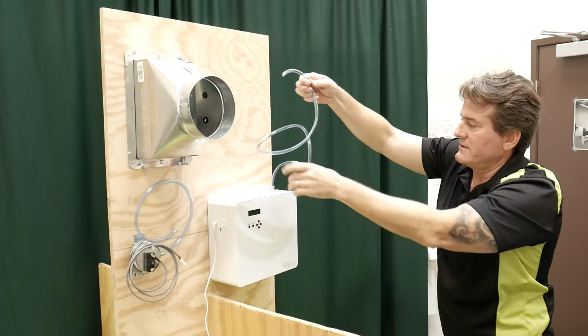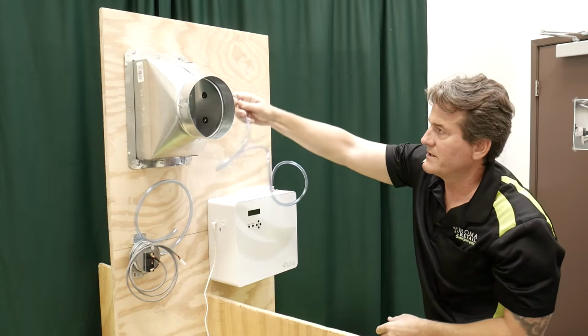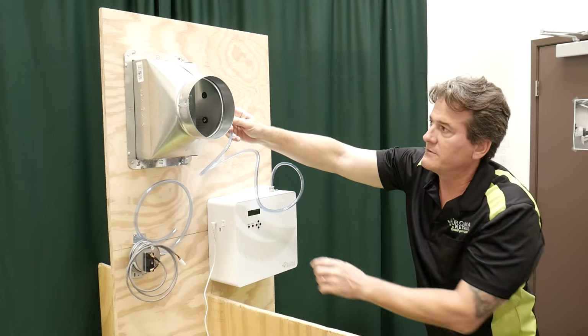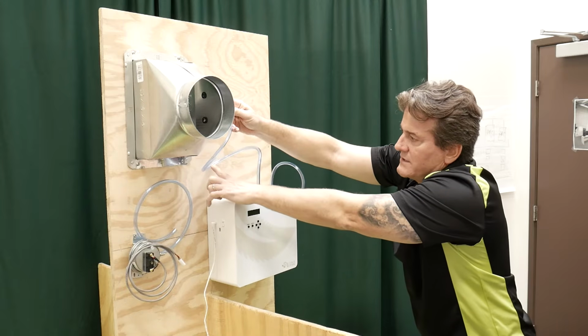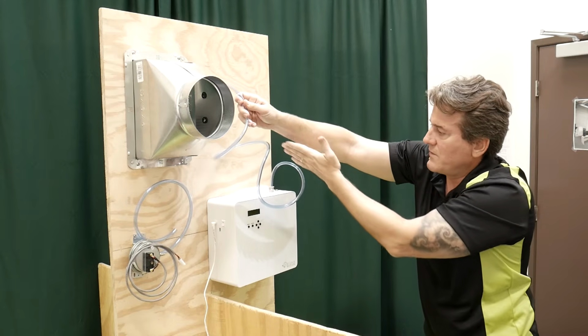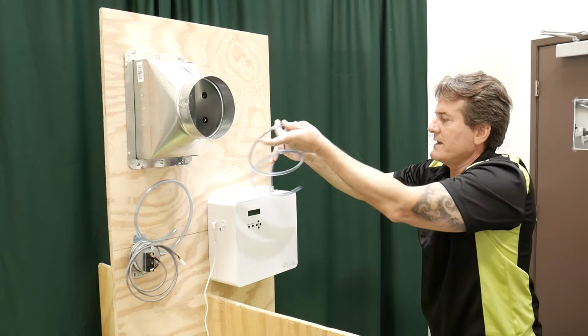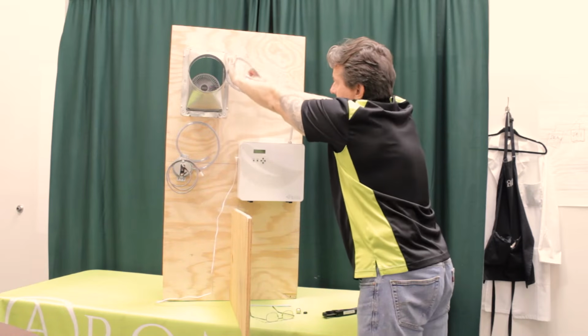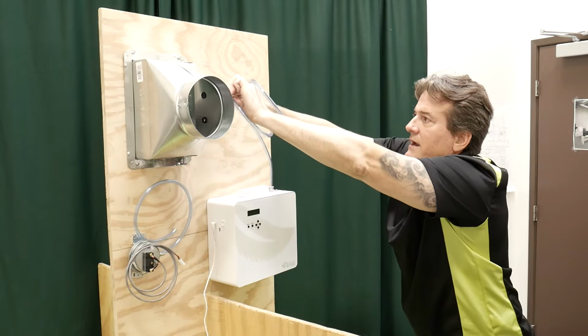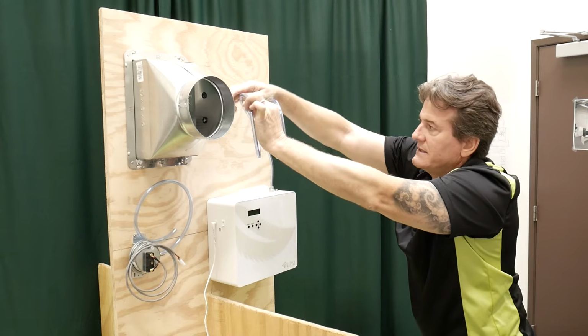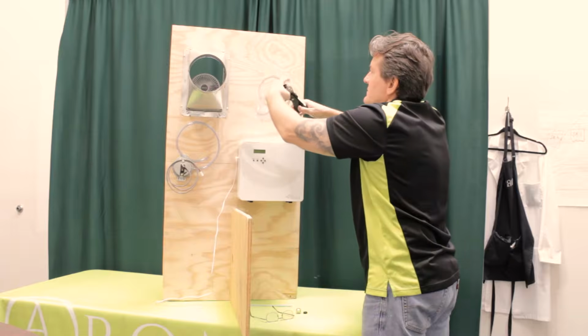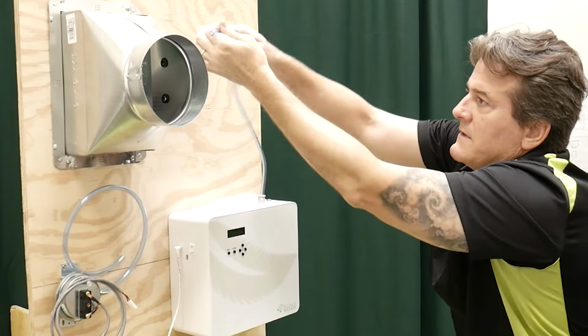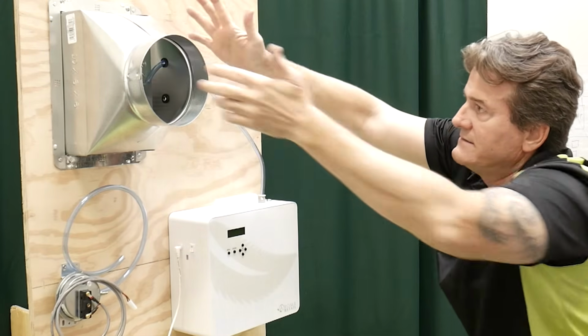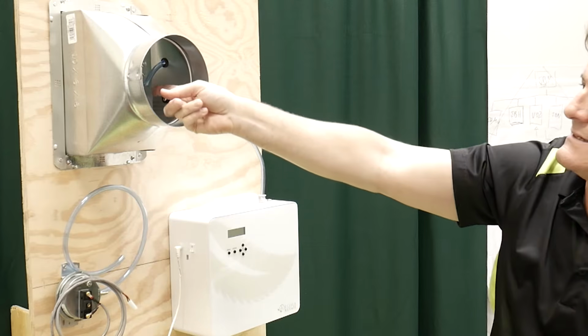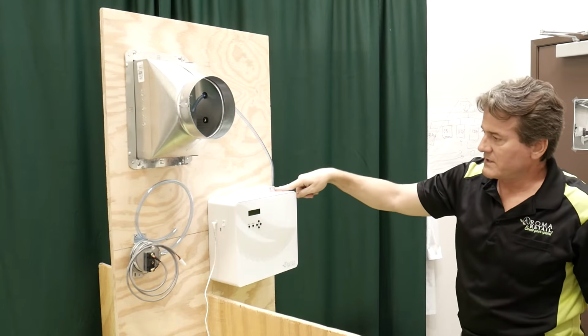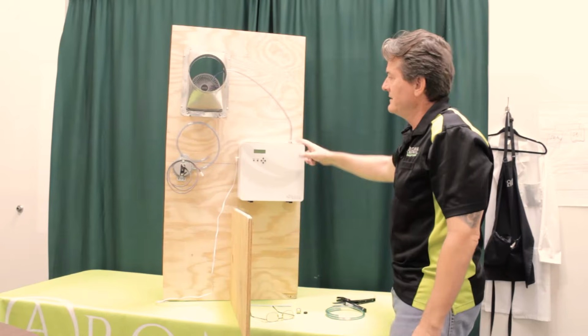And now, if I were to just run, since I was able to get my machine close to the duct, if I were to just run my fragrance tube like that, I would have a problem because any condensation of fragrance coming through here would get trapped here and again here and not be able to flow back into the canister. So I'm going to trim this to length so that I can have a nice constant slope going back into the machine, and then I'm going to allow just a couple of inches to deliver that scent into the duct. So let me size that up, and then I'll trim that tube there and push it into the duct a couple of inches, and you see now I'm good to go, where I'm delivering the scent in here in front of my fan, and I've got a way for the fragrance to go back into the canister if there's any condensation. And now I'm ready to scent.